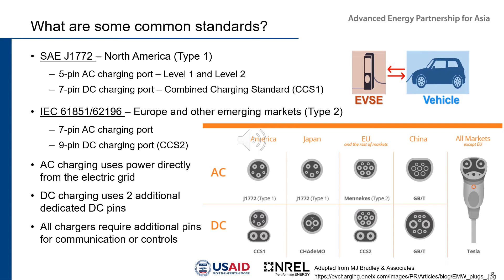AC charging Level 1 and 2 offer a wide variety of output power options based on operating voltage and maximum current. Level 1 options are the lowest power options and provide the simplest installation process, with 120 volt outlets readily available in most homes and commercial buildings. Level 2 requires a higher voltage service from 208 to 240 volts, which is also common but may require more expensive installation costs.